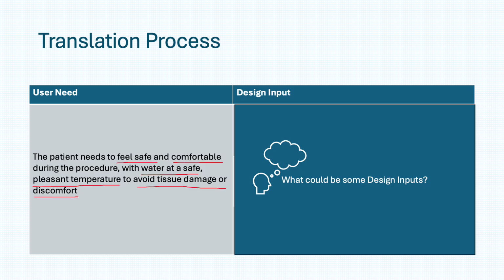The technical team will next have to identify how many design inputs they can come up with based on this user need, or how they can translate this user need into different design inputs. Now, there could be more than one design input, even though there is one user need, because the user need is subjective. Design input will be objective. It has to be measurable, verifiable. So let's take a look.